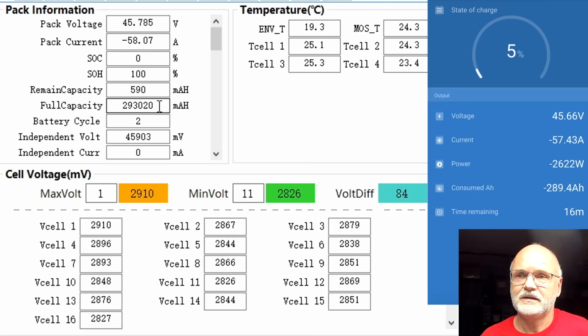45 volts, or we may see a low voltage disconnect of the inverter this time. Who knows? Cell number 11, number 9, number 14, still 3 cells in the race for the lowest voltage cell. But here's number 1, this is our highest voltage cell at the moment, and it stays like this.